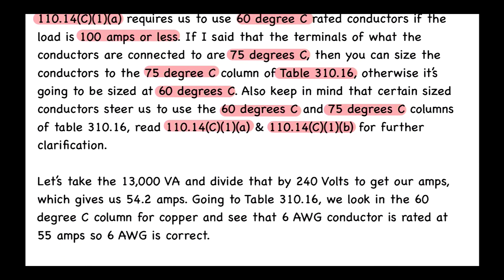We take 13,000 VA and divide by 240 volts to get our amperage: 13,000 ÷ 240 = 54.2 amps. Going to Table 310.16 and looking at the 60°C column for copper, a 6 AWG conductor is rated at 55 amps, which satisfies our 54.2-amp requirement. So 6 AWG is correct.